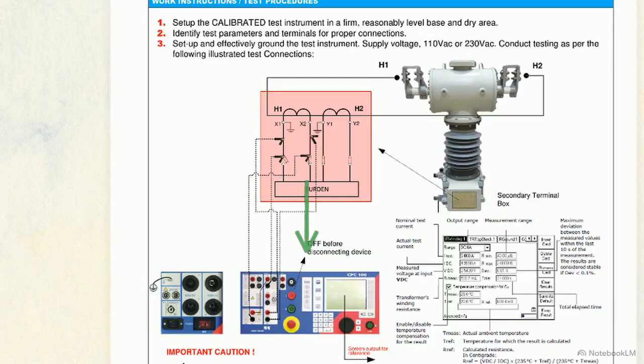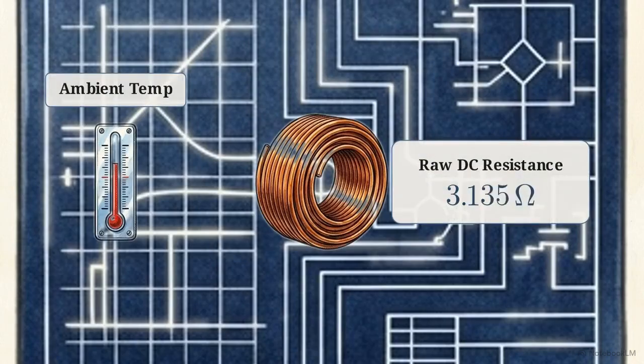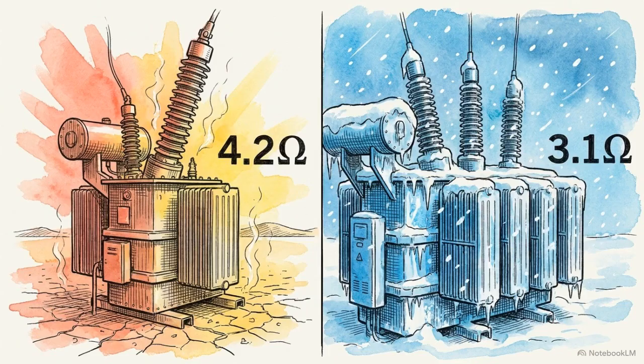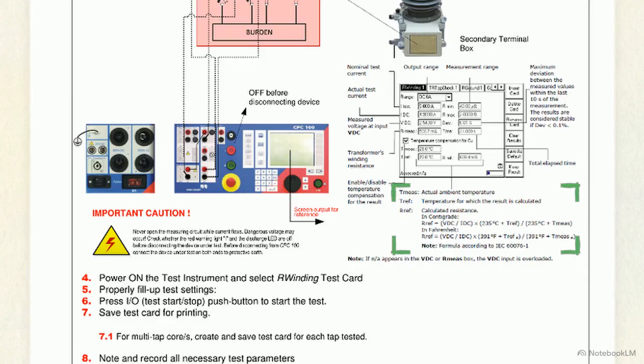The instrument applies a DC current via Kelvin leads directly into the secondary terminal block, measuring the voltage drop to calculate absolute resistance. Raw DC resistance data taken in the field is problematic. Copper resistance fluctuates heavily with ambient temperature changes, meaning a measurement taken in extreme heat will differ drastically from one taken in the cold. This interface shows the solution. The CPC-100 applies the IEC 60076-1 temperature compensation formula, automatically normalizing the field resistance values to a standard baseline temperature for accurate comparison.